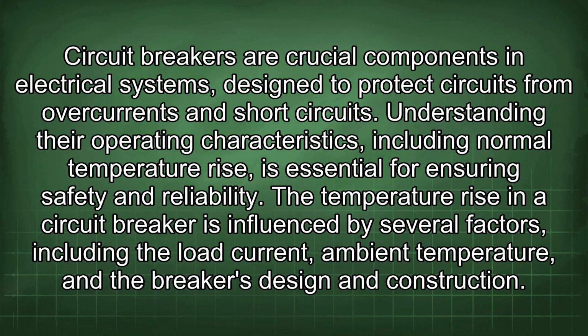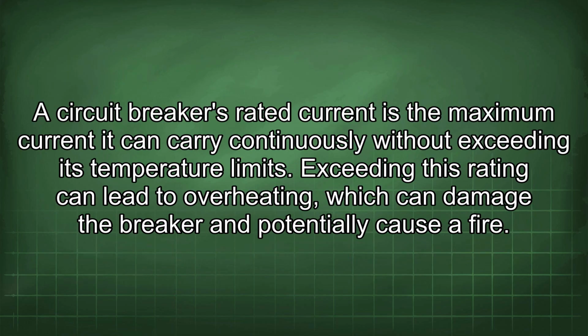The temperature rise in a circuit breaker is influenced by several factors, including the load current, ambient temperature, and the breaker's design and construction. A circuit breaker's rated current is the maximum current it can carry continuously without exceeding its temperature limits. Exceeding this rating can lead to overheating, which can damage the breaker and potentially cause a fire.